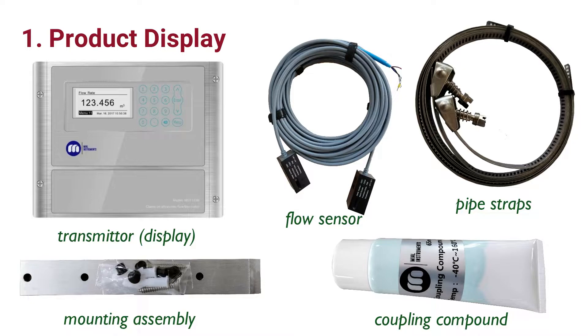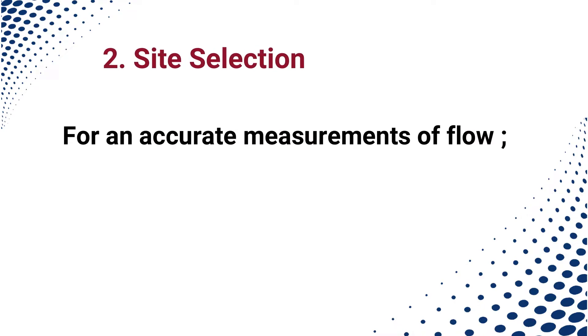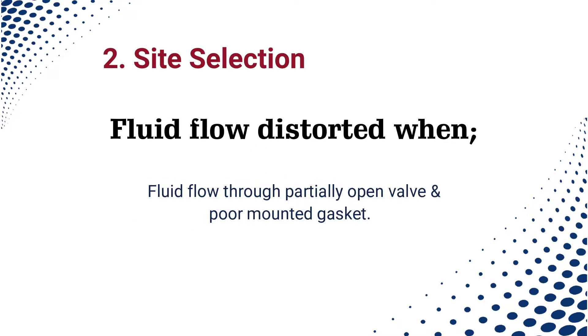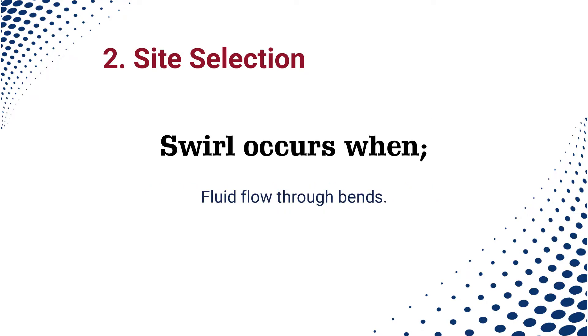For accurate measurement of flow, the fluid profile inside the pipe must be symmetrical and steady. Fluid profile distortion occurs when an obstruction such as a partially open valve or poorly mounted gasket partially blocks the pipe. Swirl occurs when the fluid flows through pipe bends. The swirl is far more difficult than distorted flow profile.